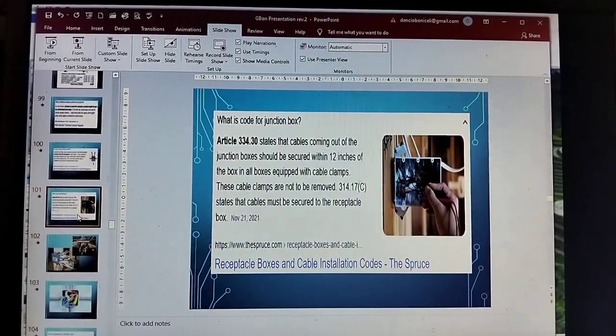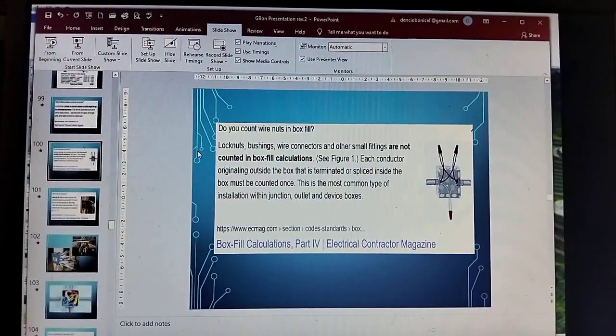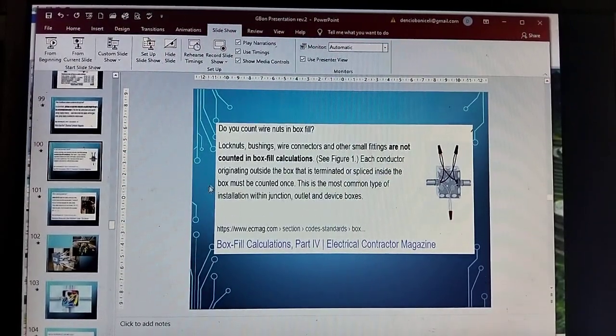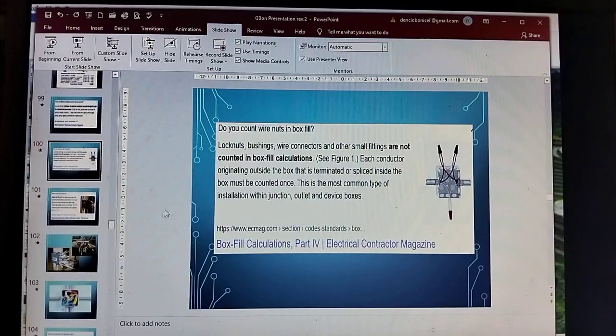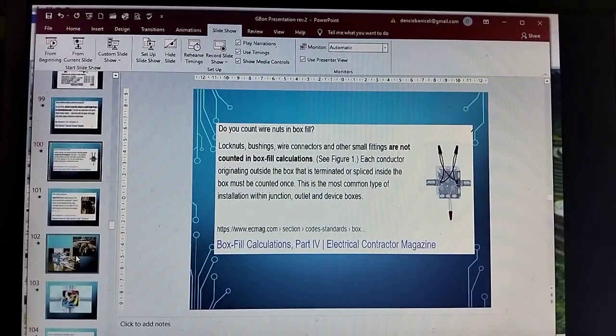Let's say here, Article 334.30 states that cable coming out of the junction box should be secured within 12 inches of the box. These clamps are not to be removed. Let's say here, do you count the wire nuts in box fill? No, because according to the standard, lock nuts, bushings, wire connectors and other things are not counted in box fill calculations. So you are going to count only the individual conductors. Okay, and fixtures.